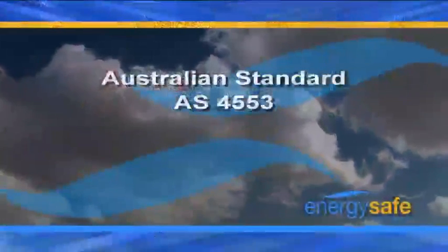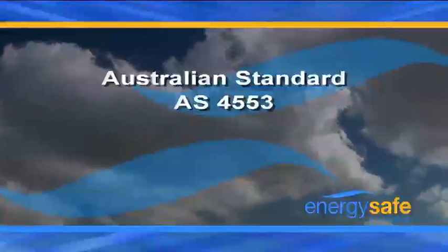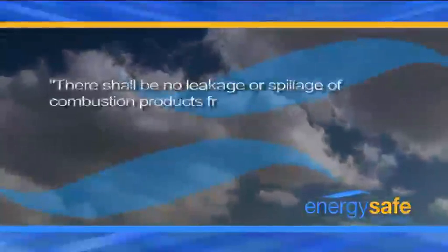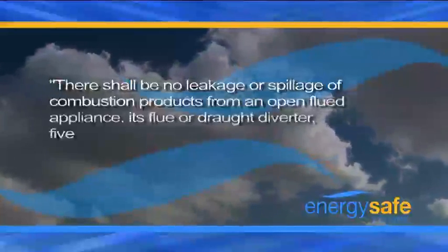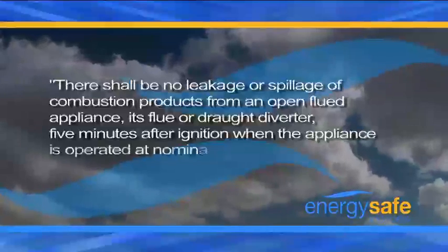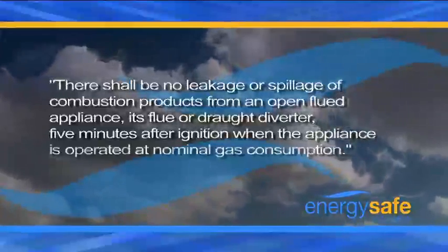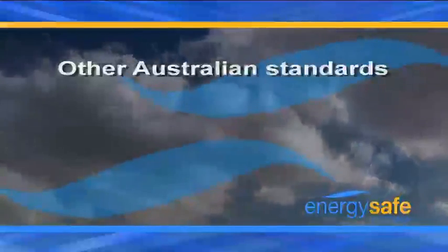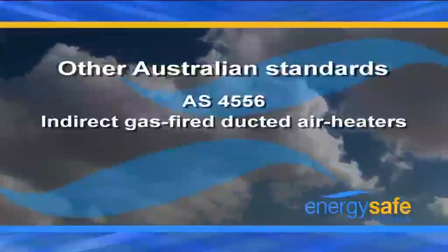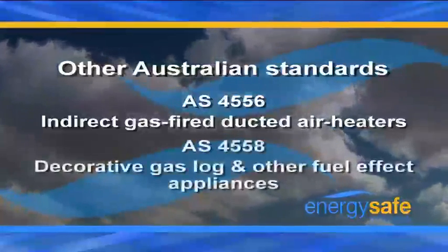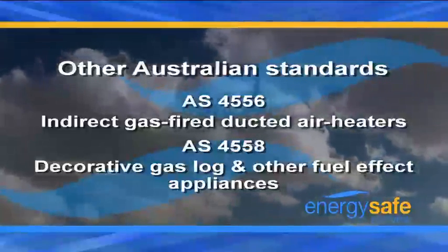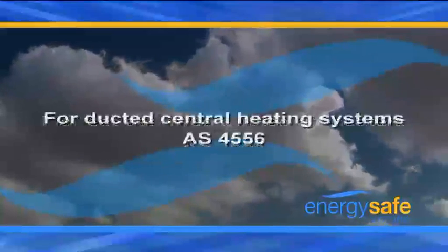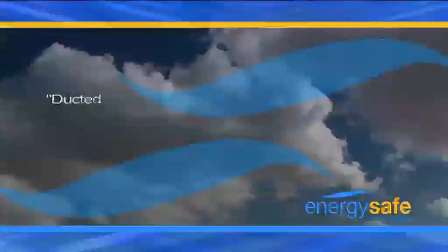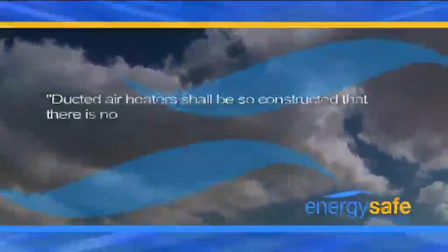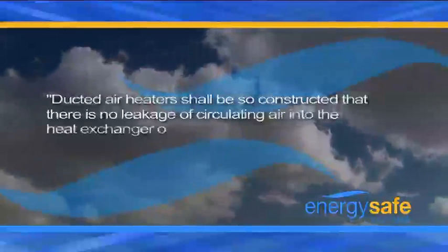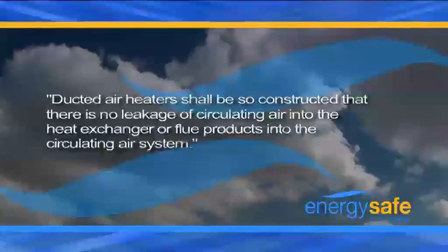Australian Standard AS4553 Gas Space Heating Appliances states, there shall be no leakage or spillage of combustion products from an open flue appliance, its flue or draft diverter, 5 minutes after ignition when the appliance is operated at nominal gas consumption. Other Australian standards that have a similar requirement are AS4556, indirect gas-fired ducted air heaters, and AS4558, decorative gas log and other fuel effect appliances. For ducted central heating systems, AS4556 states, ducted air heaters shall be so constructed that there is no leakage of circulating air into the heat exchanger or of flue products into the circulating air system.